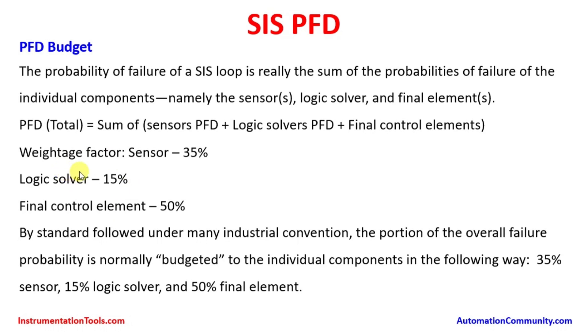The weightage factor is distributed as follows: sensors at 35 percent, logic solver at 15 percent, and final control elements at 50 percent. The reason for keeping the logic solver at the lowest weightage of 15 percent is that logic solvers are located in the non-hazardous area, in a safe location, and they have only electronic components operating at a high level in the system. Therefore, the probability of failure is very low.